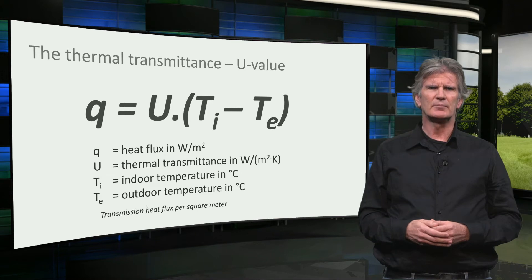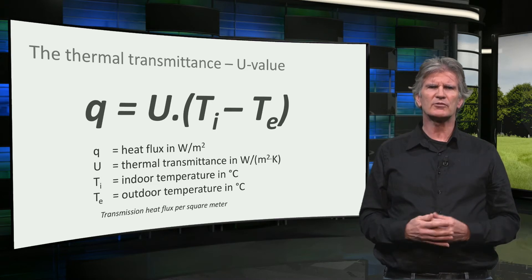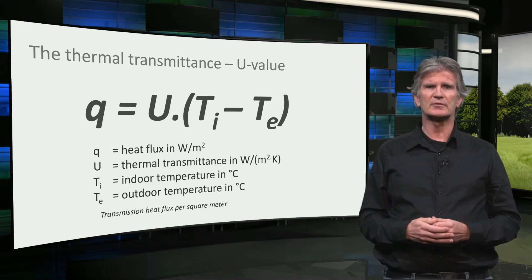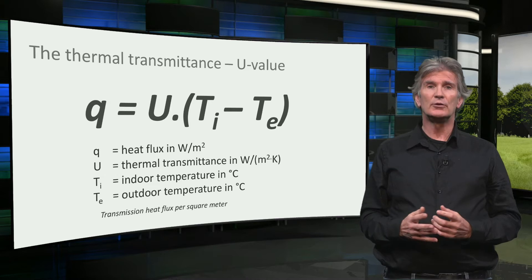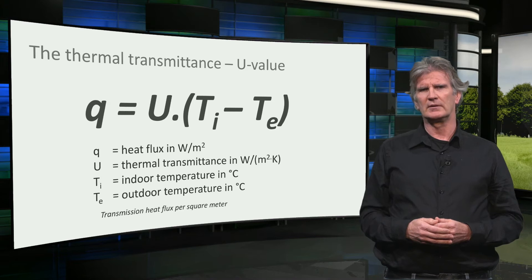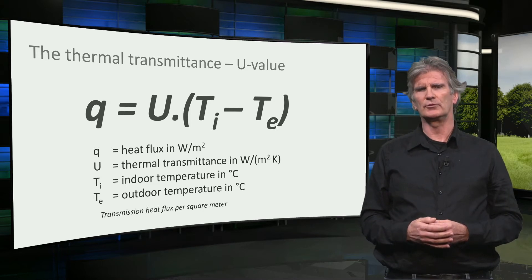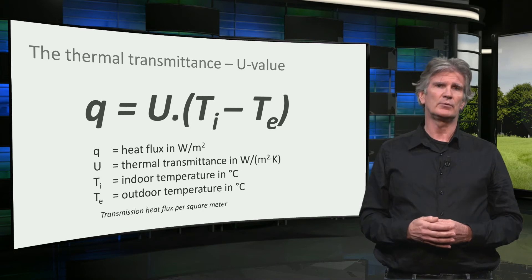The transmission heat loss through a part of the building envelope can be calculated with this formula. The heat flux through the building envelope in watts per square meter equals the U-value of the building part times the temperature difference between indoor and outdoor. The U-value is the thermal transmittance of the building element, with the unit watt per square meter per kelvin. It says how big the transmission loss per square meter is per degree temperature difference. So the lower the U-value, the better.